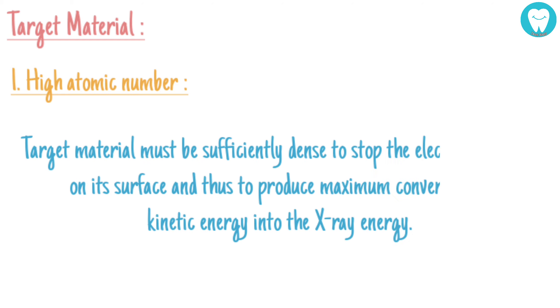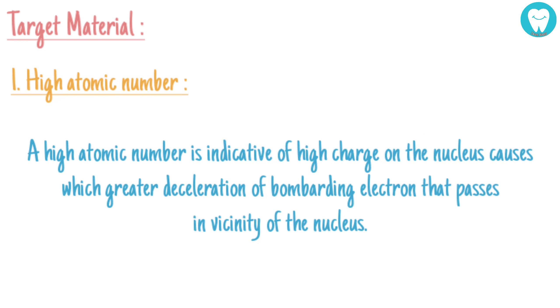The ideal target material should have: number one, high atomic number. Target material must be sufficiently dense to stop the electron abruptly on its surface and thus produce maximum conversion of kinetic energy into X-ray energy. A high atomic number is indicative of high charge on the nucleus, which causes greater deceleration of bombarding electrons that pass in vicinity of the nucleus. It results in production of high energy characteristic radiation.